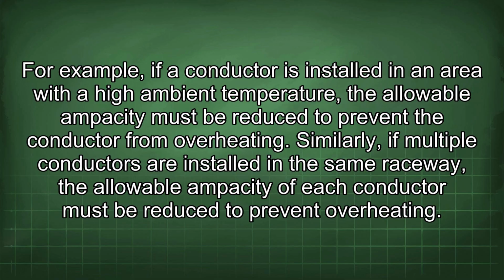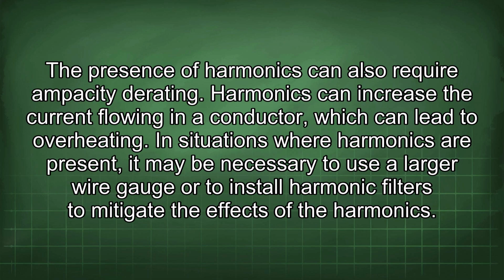Similarly, if multiple conductors are installed in the same raceway, the allowable ampacity of each conductor must be reduced to prevent overheating. The presence of harmonics can also require ampacity derating. Harmonics can increase the current flowing in a conductor, which can lead to overheating. In situations where harmonics are present, it may be necessary to use a larger wire gauge or to install harmonic filters to mitigate the effects of the harmonics.